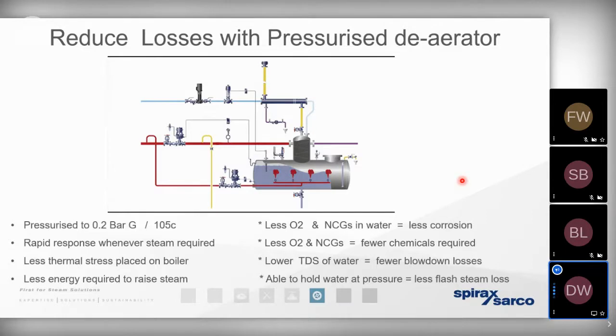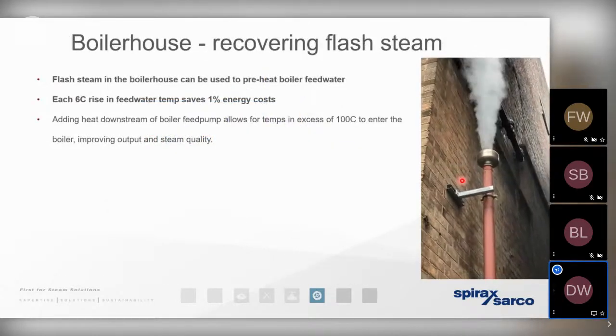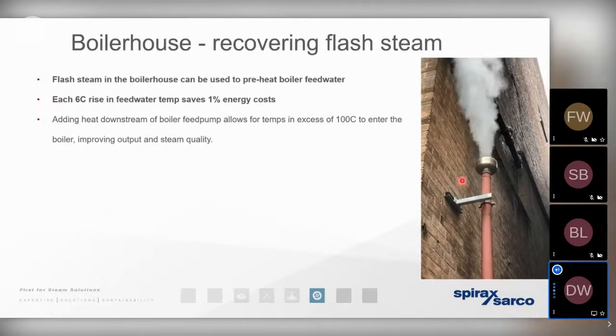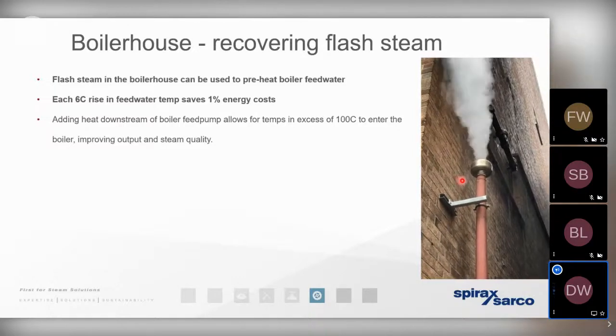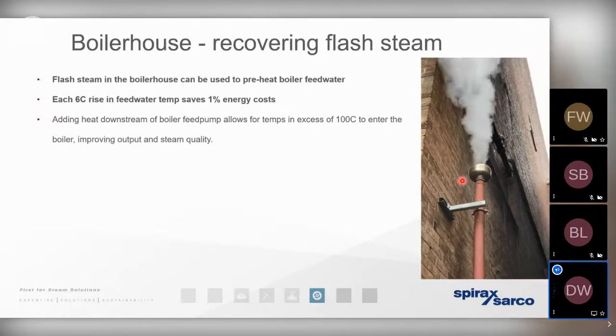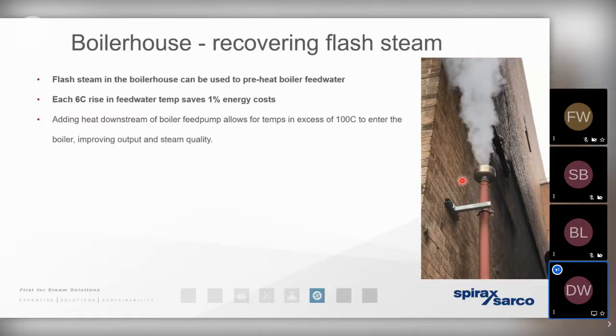And this really is increasing in popularity, especially in the food, beverage, and pharmaceutical sectors that require a massive steam supply to be supplied to the process at a consistently better condition than plant steam. But we also know, coming back to those flash steam losses, that flash steam venting away to atmosphere is inevitable. The little video over towards the right hand side of the screen, that flash steam vent, is very easy to identify, especially on a cold day.